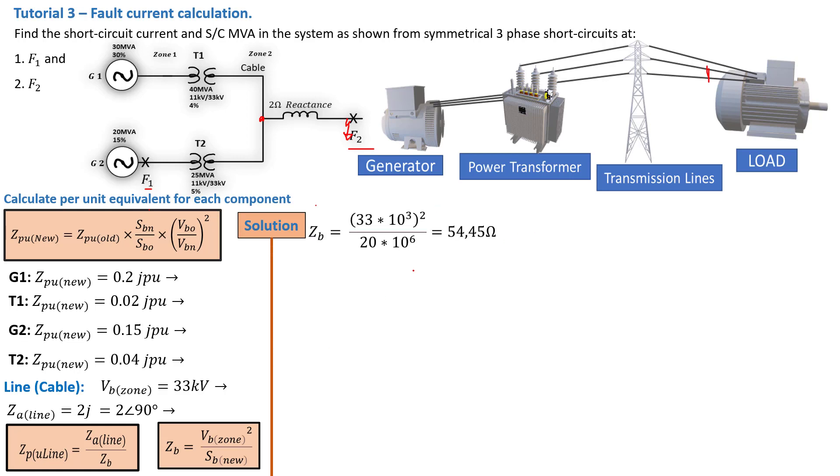Moving forward, ZB is then equal to 33, that is the zone voltage squared in kilovolt squared, over the 20 MVA that we selected for this system. That gives us an impedance of 54.45 ohm. From there we can then calculate the Z per unit of the line. That is 2, which is Z actual divided by ZB, and we find Z per unit of the line of 0.0367J.